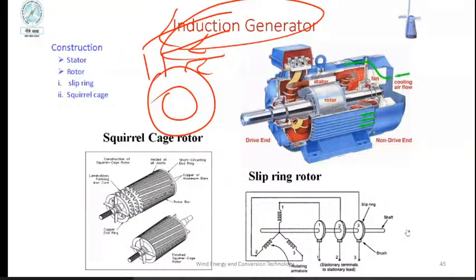Okay right sir, so the induction generator construction has both the stator and the rotor. The stator is always connected to the grid, while the rotor has no connection - it's separate. It's a squirrel cage induction generator with a wall. So when it drops out from the grid, it acts as a motor. Once it acts as a motor, it creates electromagnetic force, and once the electromagnetic force is created, it induces EMF to the rotor.